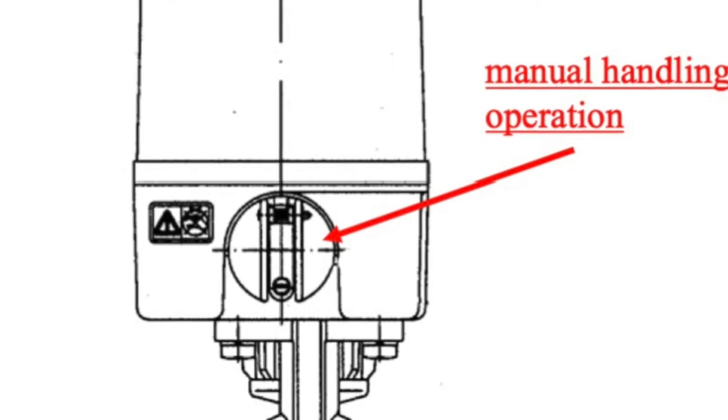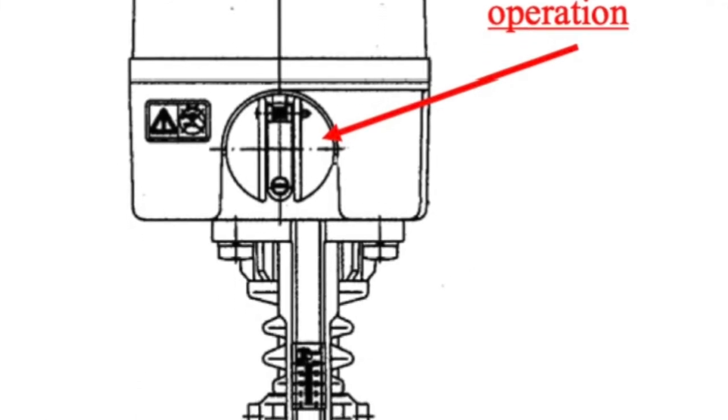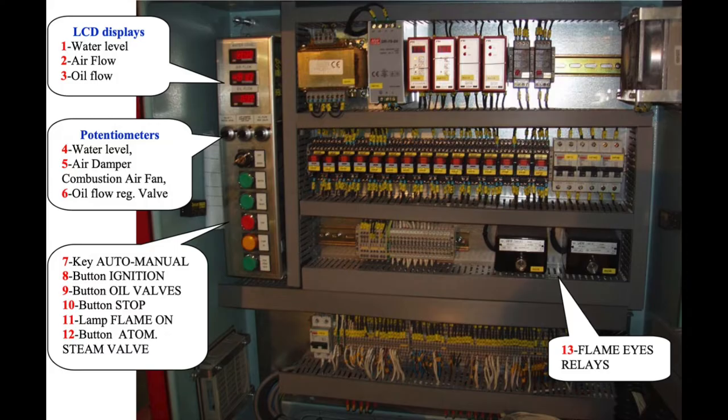This adjustment will be made manually by adjusting the fuel automatic regulating valve and some of the ball valves for the return. After that, we verify that our fuel temperature varies from 115 to 120 degrees and make the appropriate adjustments from the preheaters.